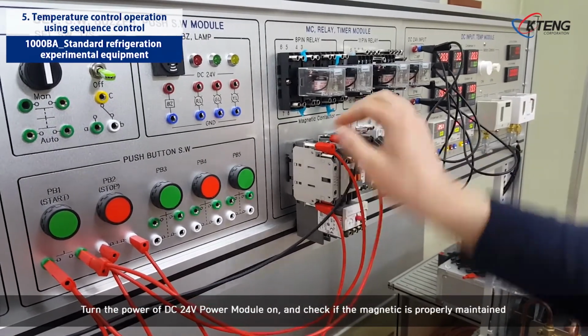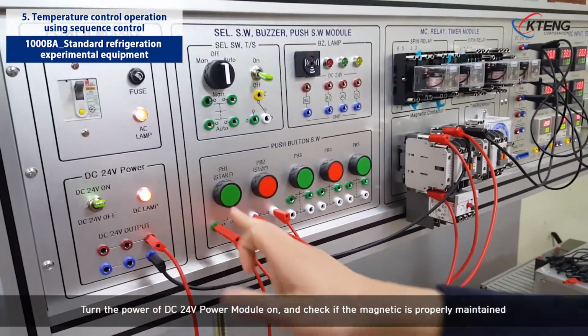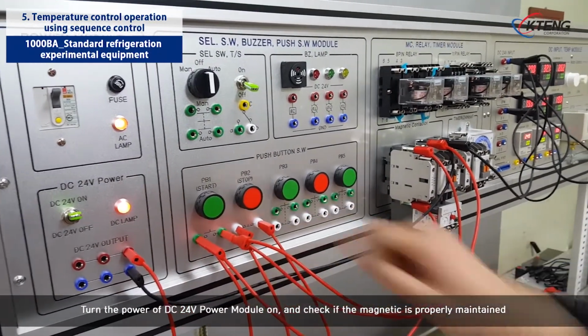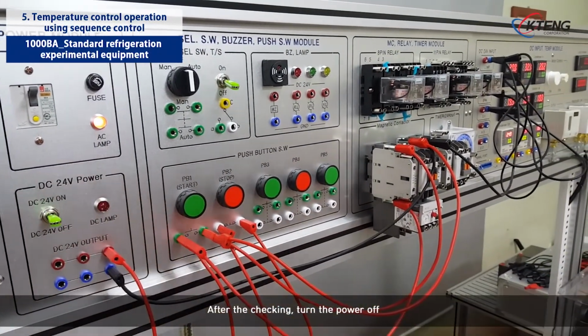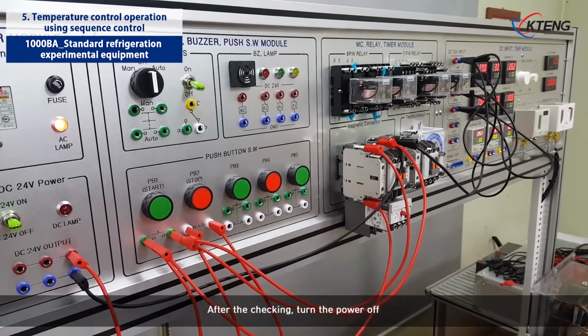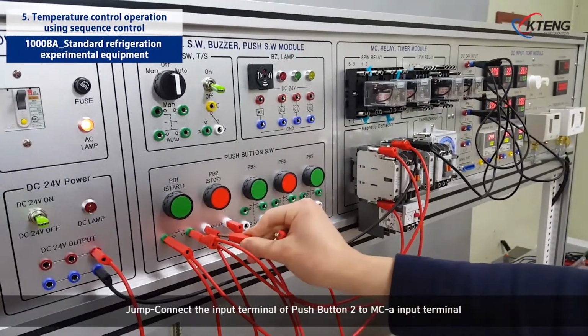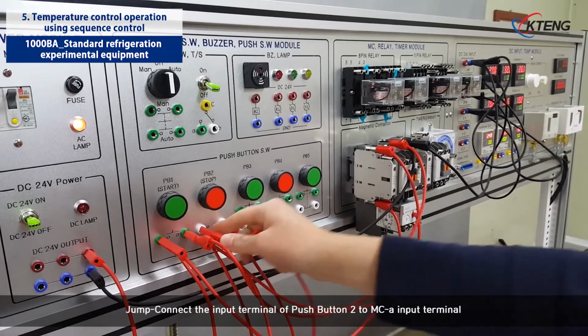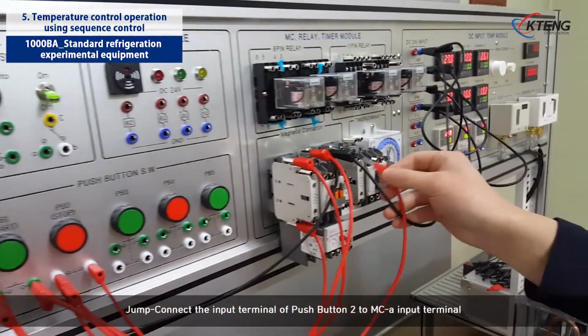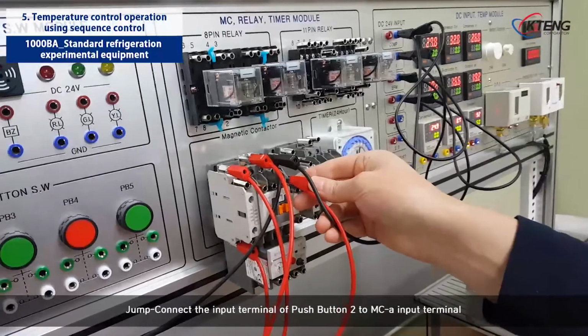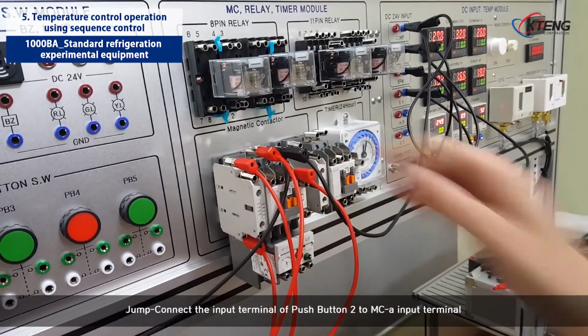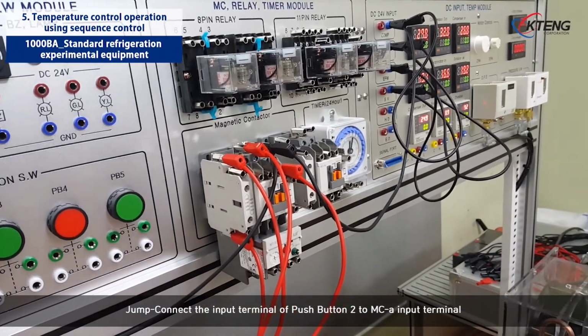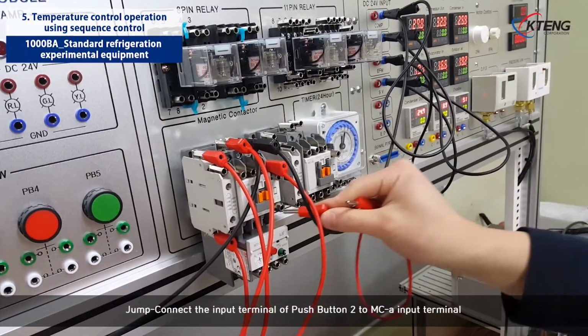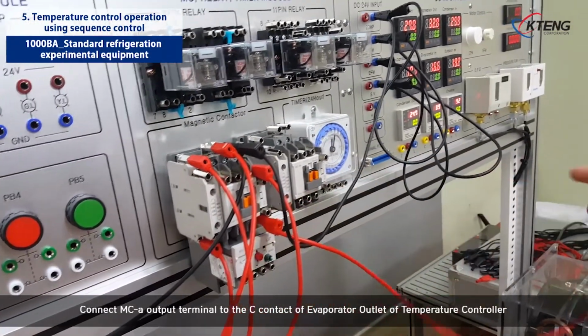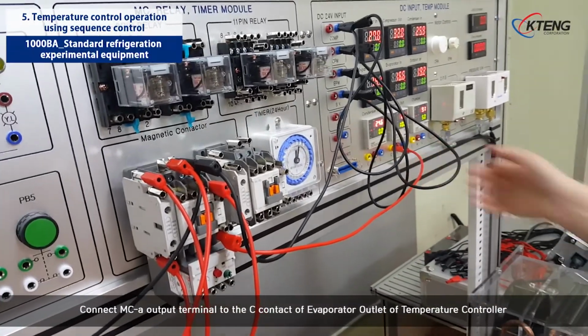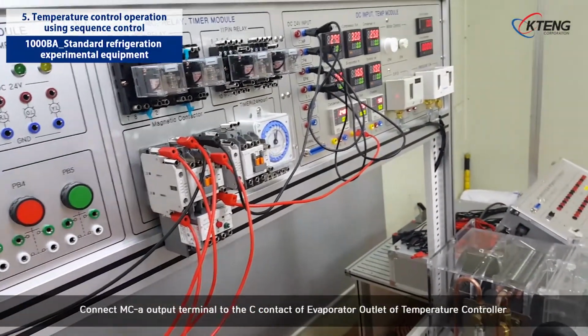Turn the power of DC 24-volt power module on and check if the magnetic is properly maintained. After the checking, turn the power off. Jump connect the input terminal of push button 2 to MCA input terminal. Connect MCA output terminal to the C contact of evaporator outlet of temperature controller.